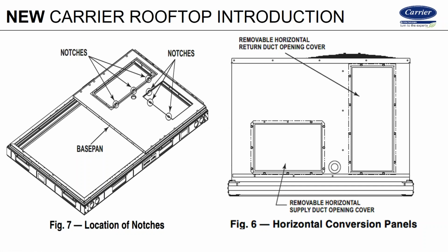And just to complement that explanation, your Y1 signal, if the outdoor air is suitable for cooling through the economizer, is going to run cooling using outside air. Now, if that outside air isn't satisfying the space, then you get a Y2 call. That Y2 call is routed to bring on the compressor. So now you have the compressor running with the economizer, and then the economizer will slowly throttle back down closer to its minimum position because your compression is typically making the supply air point. So yes, like Ryan said, you absolutely need two-stage to get proper operation, even if it's a single-stage unit.